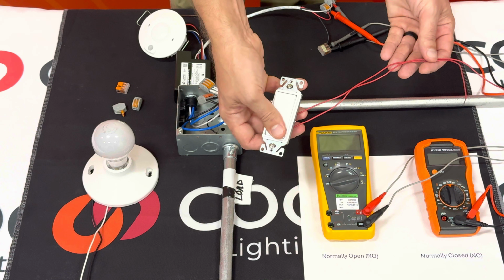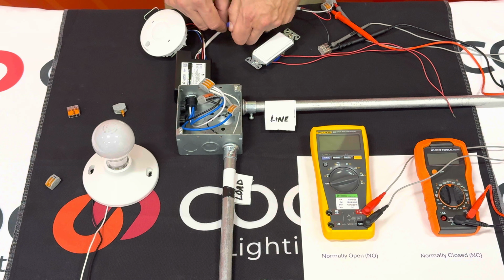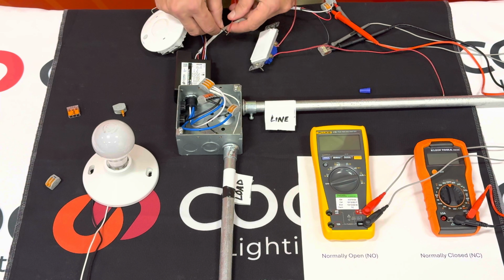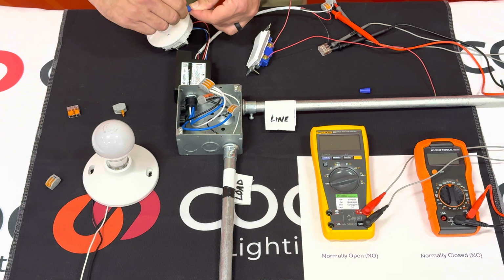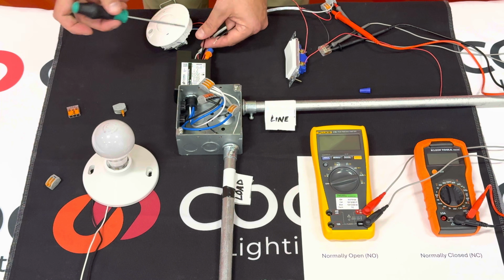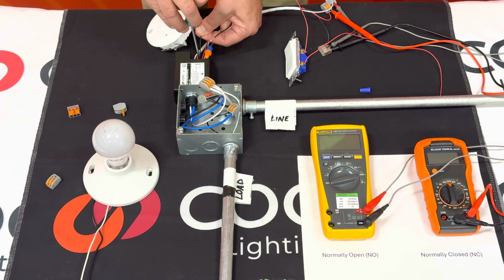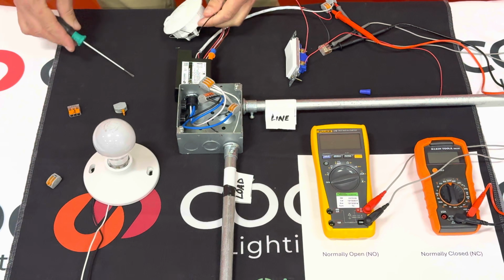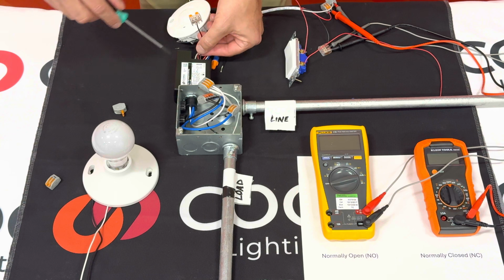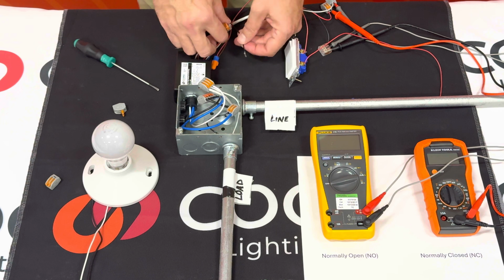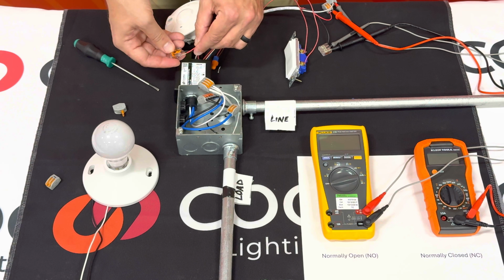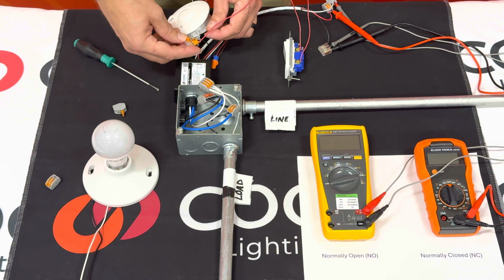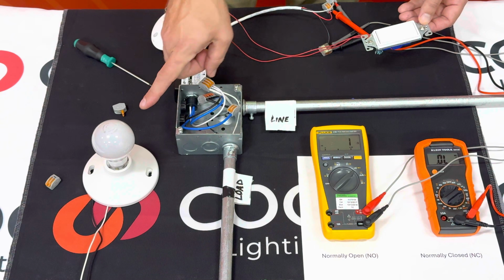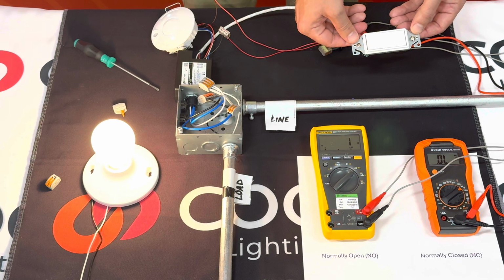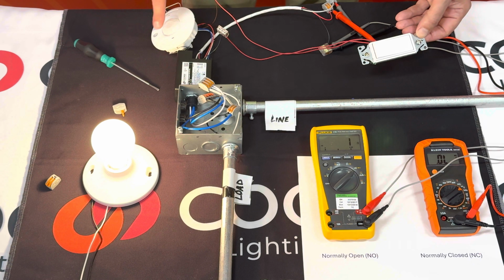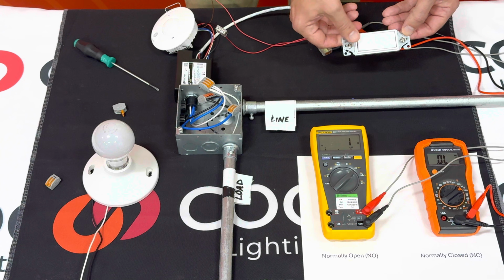GMDS momentary switch wiring. Connect one terminal from the GMDS to the brown wire from the OCSL. Connect the other terminal from the GMDS to GND on the RSP-V. Note that GND is also connected to the black wire from the OCSL. With the RSP-V powered up, the sensor and GMDS momentary switch can now both control the load.